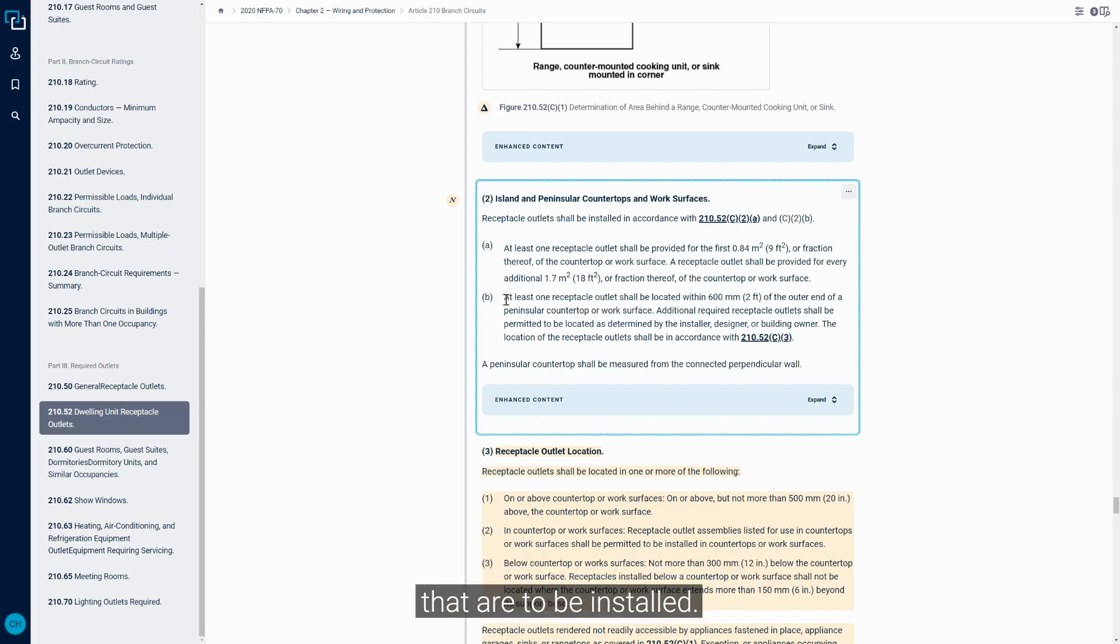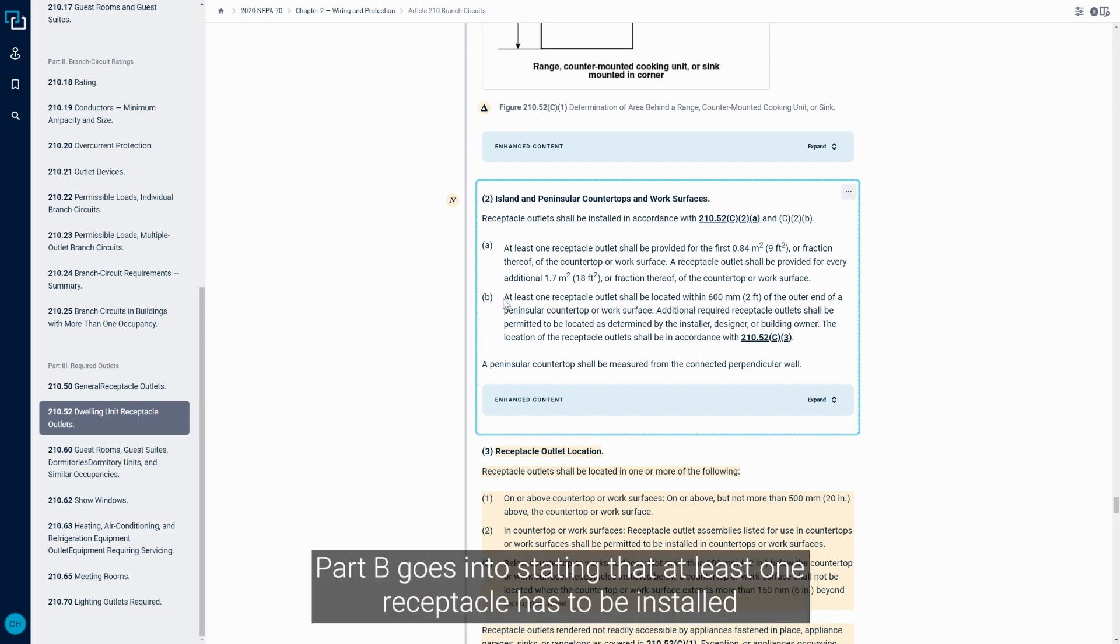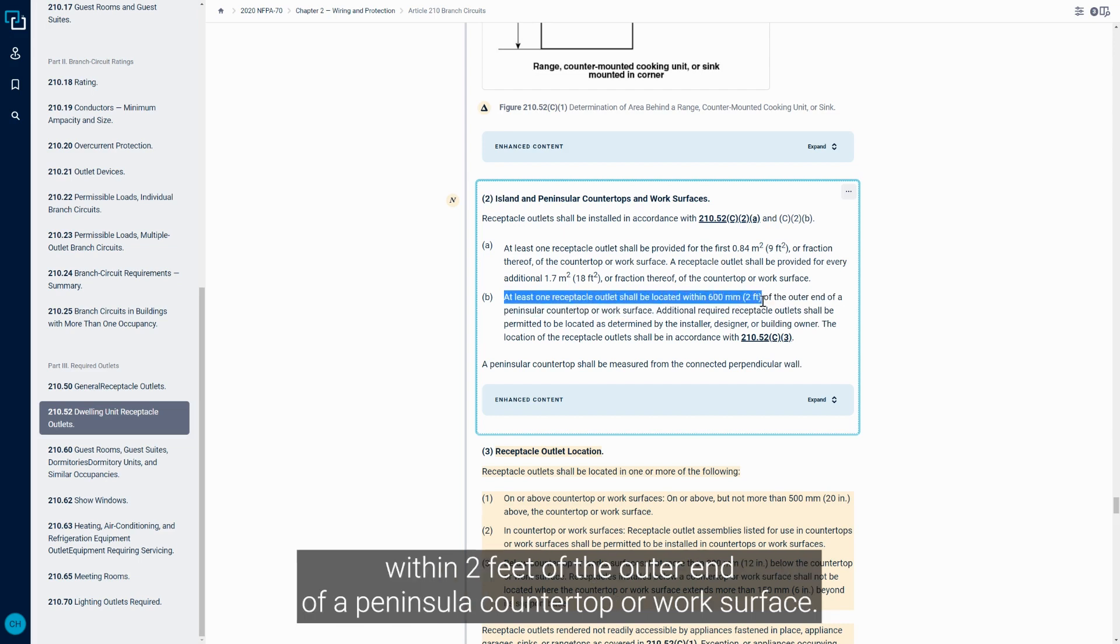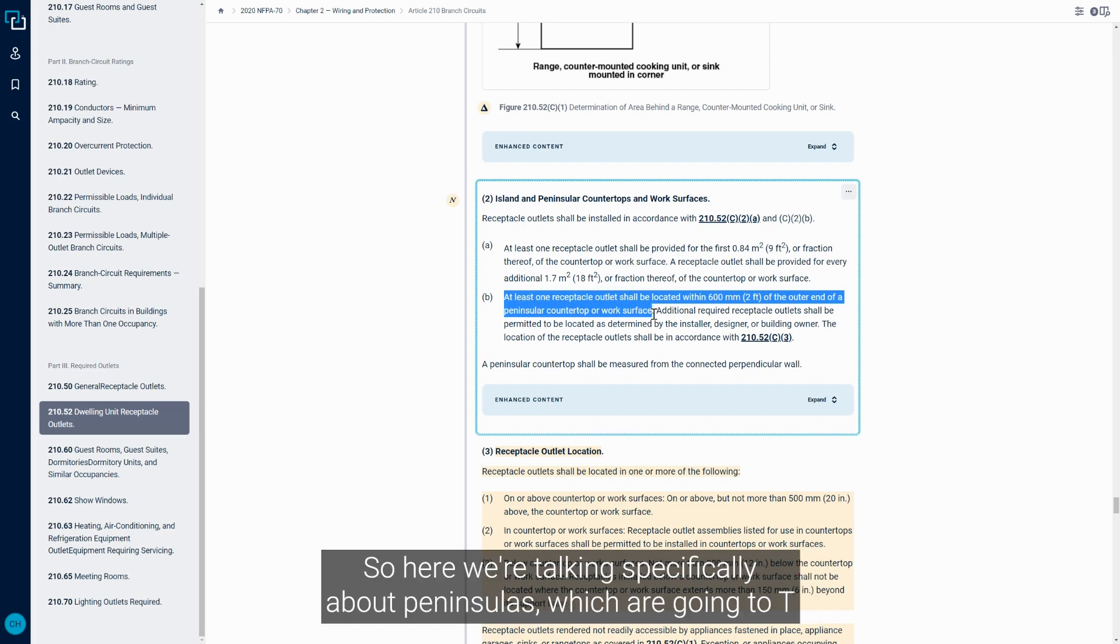Part B goes into stating that at least one receptacle has to be installed within two feet of the outer end of a peninsula countertop or work surface. So here we're talking specifically about peninsulas, which are going to T or L off of another countertop and protrude out into the room.